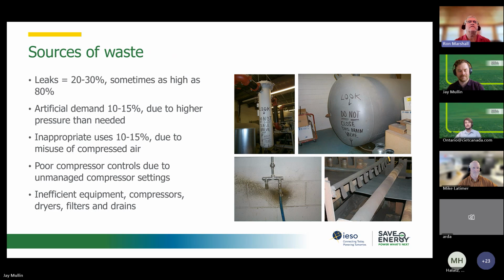There's artificial demand. Artificial demand is kind of strange. Remember, I just said that feeding the plant at a higher pressure causes more air to flow, right? The load in a plant just looks like an orifice if it's unregulated, right? And the higher pressure you feed an orifice, the more air flows. The relationship is about 1% more flow for every 1 psi, right? So that we call artificial demand. So if you're feeding the plant higher pressure than desired, 10 to 15 psi on average, extra flow is feeding into the plant. And then inappropriate uses, usually you can find 10 to 15% of inappropriate uses that could possibly be optimized or eliminated, right, to save the flow.